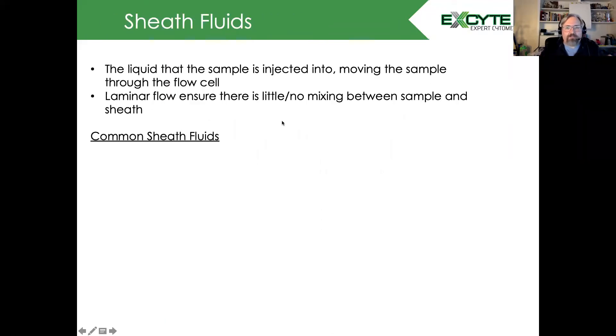Sheath fluid is the liquid that the sample is injected into, moving the sample through the flow cell. We require laminar flow to ensure there's little or no mixing between the sample and sheath fluid, and we'll talk about that in just a second.